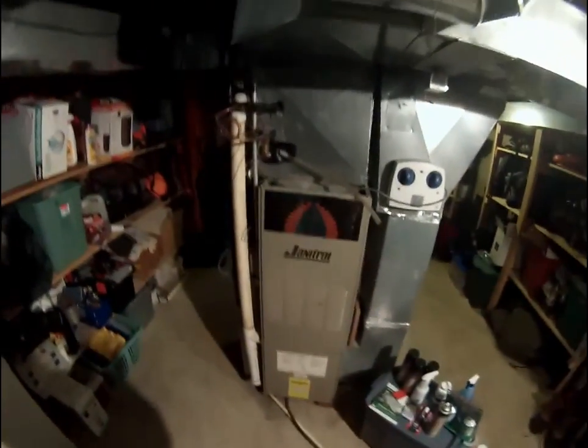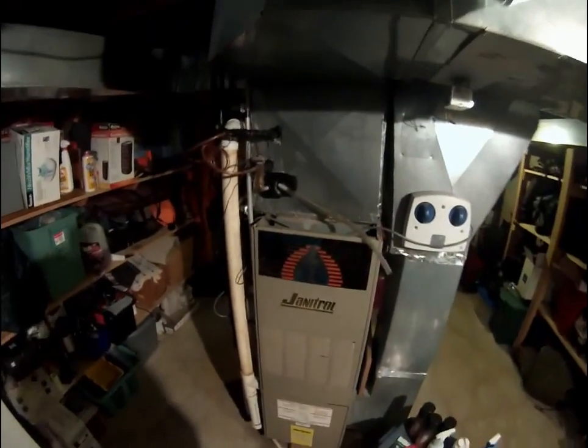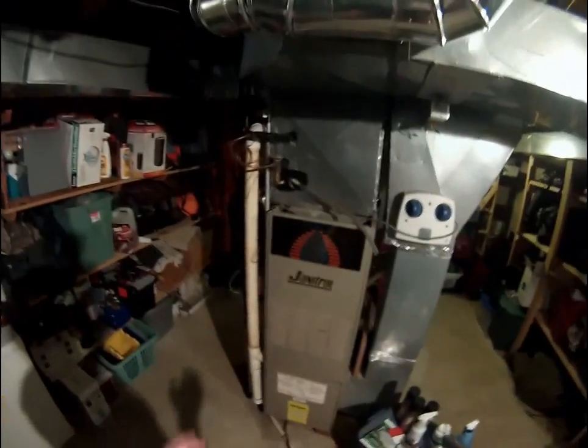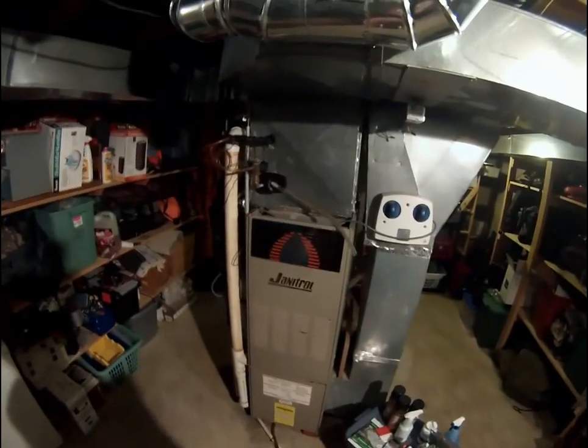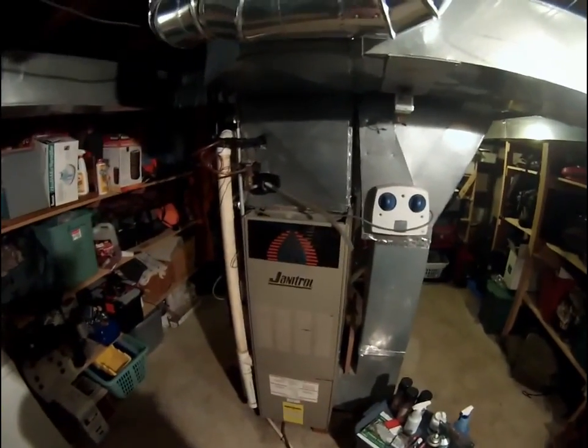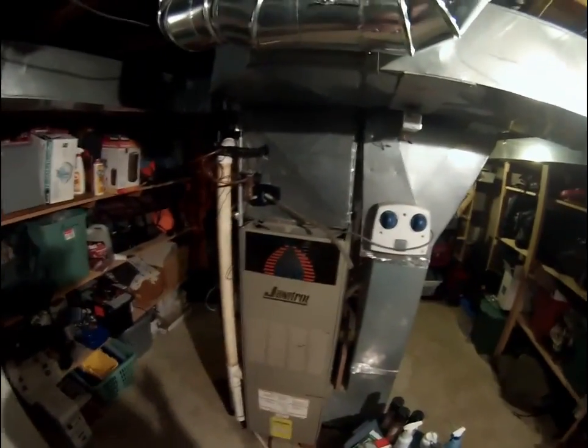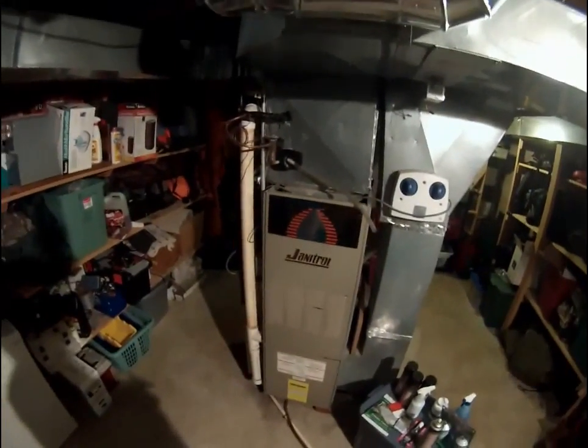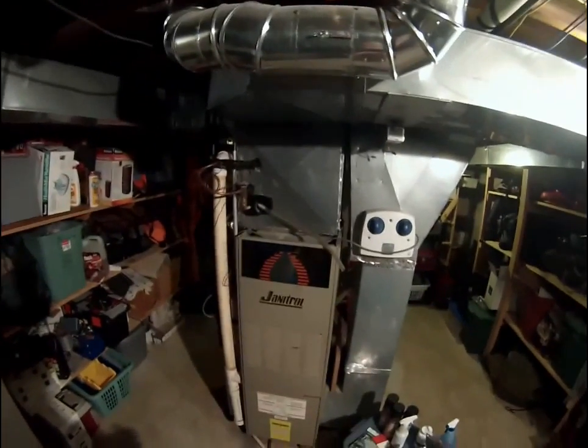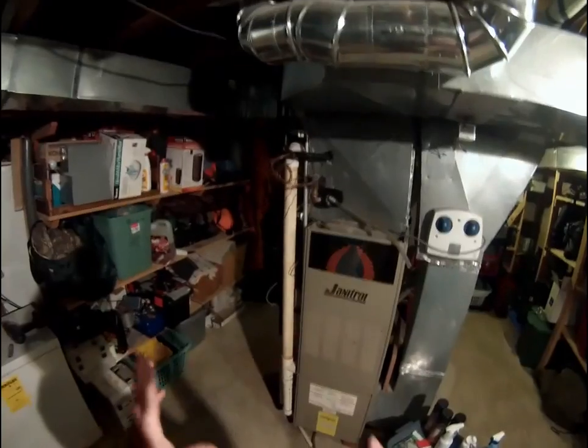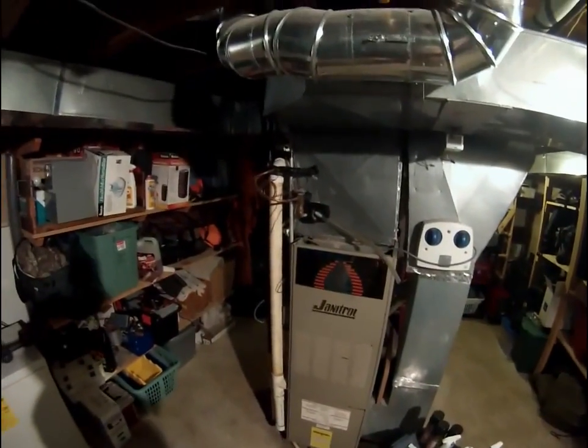Again, the airflow. The second thing that can cause it, if you've done all this and you're confident that you have good airflow and you get everything cleaned up and you go to run it and it still continues to freeze up, then you may have a Freon problem, as far as low Freon and a Freon leak. They can either be in the evaporator coil or outside. If it's a real large leak that's losing more than 2 to 3 pounds, say in a season, you're definitely going to have to get a tech out there to find and locate the leak.